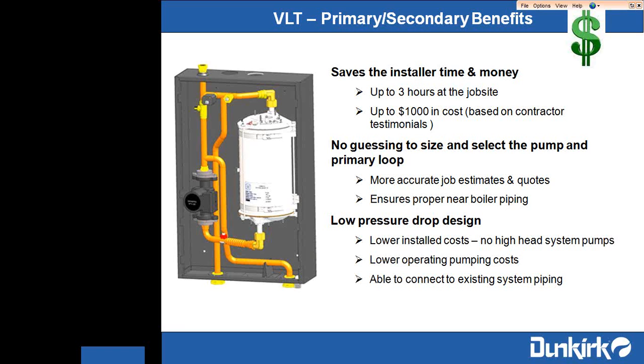The onboard circulator with the boiler is meant to drive water through the heat exchanger. So the only circulator the contractor will need will be for his central heat zone, and that's a Taco 007 or Grundfos equivalent. He can even use the circulator that's pre-existing from the job as long as it's clean and functioning. I'm just going to jump in as I can't resist it.